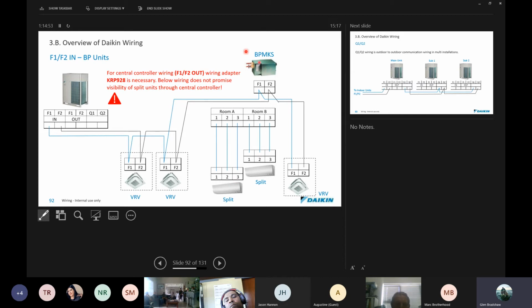Remembering that in VRV, the indoor units have an expansion valve. When we talk about our splits or our Sky Air product, the expansion valve is in the outdoor unit. So what this box does is provide an expansion valve for the indoor. You must remember that the F1, F2 connects through any VRV indoor F1, F2 into the BP box's F1, F2. That then in turn has a 3-wire connection.